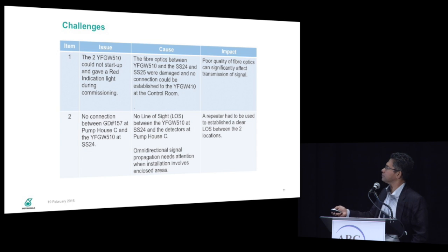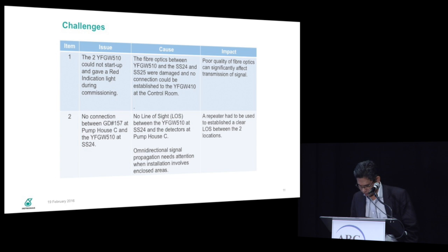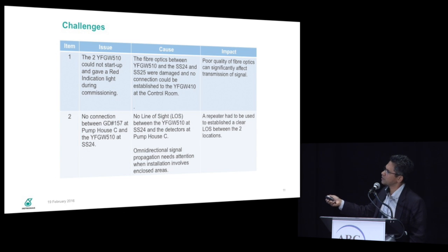The challenges that we encountered. The transmitters could not start up and gave a red indication light during commissioning. This is the gas detector, this is the transmitter. The cause was that the fiber optics between the transmitters and the receivers were damaged, and no connection could be established to the receivers at the control room. The impact was that poor quality of the fiber optics can significantly affect transmission of the signal. So during that commissioning, we encountered poor quality of fiber optics because we use the fiber optics to transmit the data.